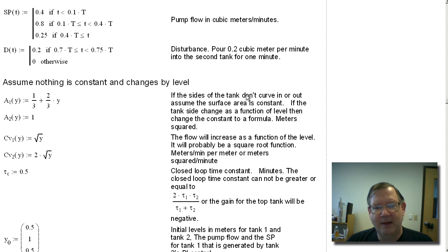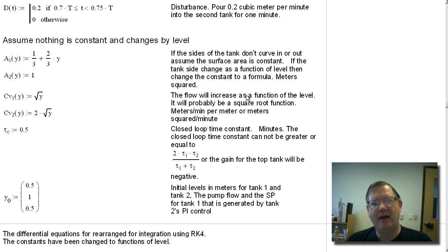Now, up to this point, I have assumed that all the gains and all the time constants are really constant. And that's one of the assumptions that people make, well, that's a poor assumption in a lot of cases, especially on tank control. You can see that on a normal hydraulic system, the flow through an orifice or a valve is proportional to the square root of the pressure drop across it, which is going to be proportional to the head, or elevation of the fluid in the case of our tanks.